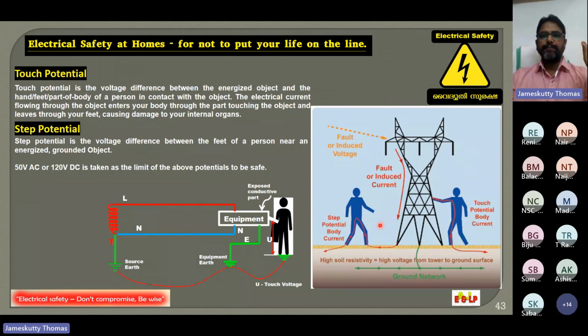In the second case, he is not touching the tower at all, just walking near it. Between his feet, a potential difference develops due to the potential gradient from the tower, which is the energized object. Due to the voltage in the tower, there is a potential gradient through the ground, and as he walks through it, a potential difference develops between his feet, causing an electrical accident.